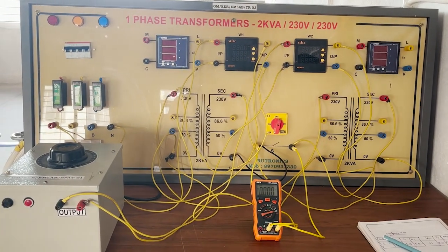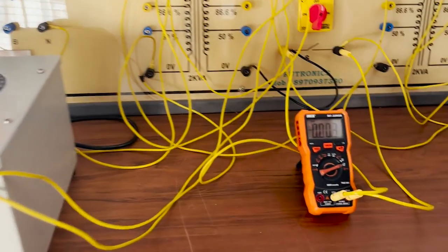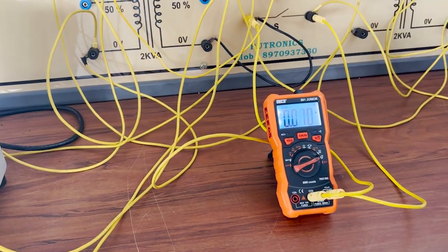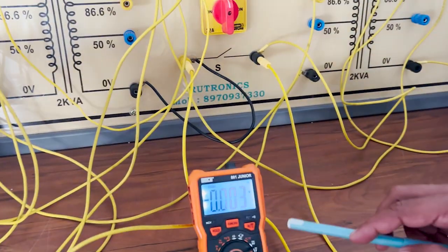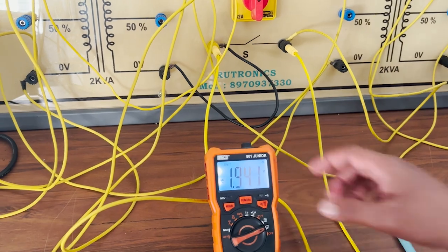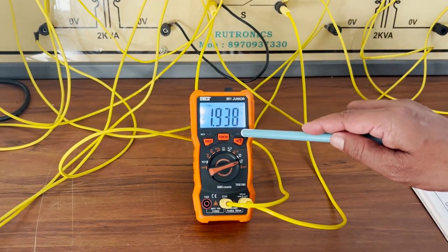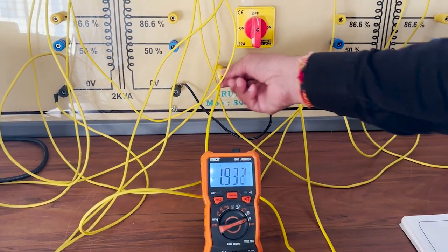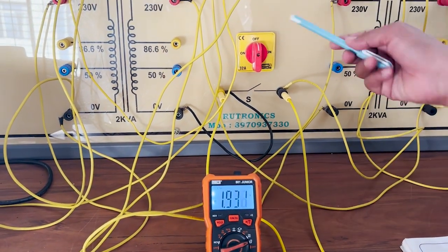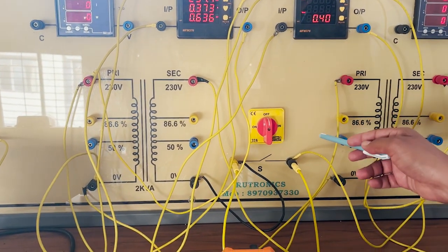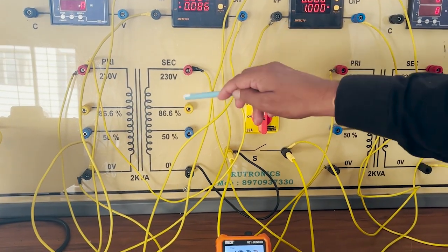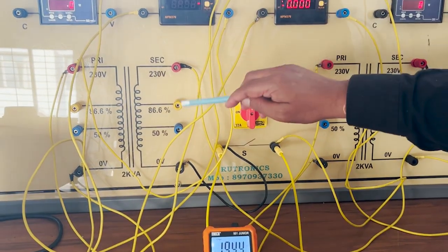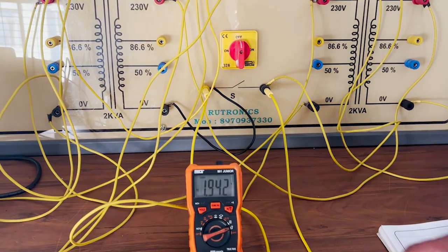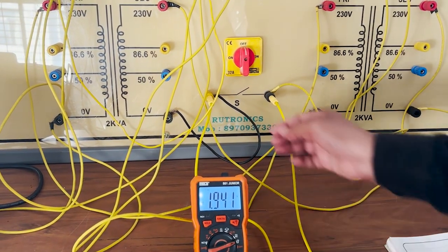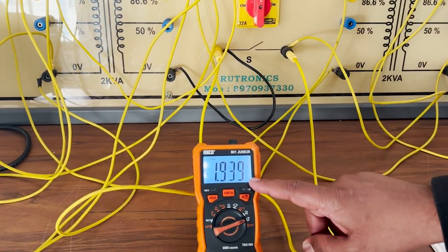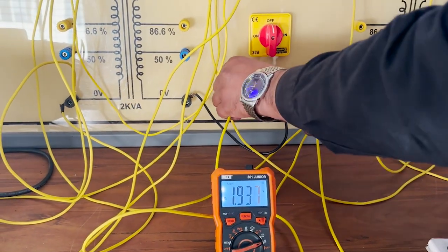After making the connection you have to close the switch. Once you close the switch, we have to see what is the voltage across the voltmeter, that is across the switch. If it reads less than 10 volts across the switch, then we have to disconnect the terminals of the voltmeter. Suppose it reads double the voltage, that is 230 plus 230, 460 volts, then you have to interchange the terminals of any one of the transformers on the secondary side, that is S1 to S2 or S2 to S1. Now we can see the voltmeter reading is less than 10 volts, that is 1.9. Now we can disconnect the terminals of the voltmeter.